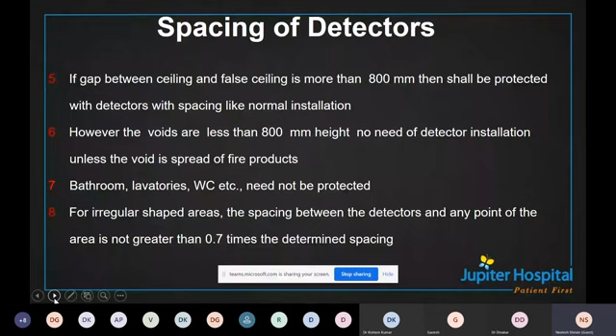So as per the norms, if this is the case, then we need to make sure that we put smoke detectors above the false ceiling and below the false ceiling also. This is mandatory nowadays. So please make sure that if your distance is more than 800 mm, you put both sprinkler and smoke detector above and below the ceiling. Similarly, there is no need to put detectors in a bathroom, lavatories or WC. For any irregular shaped areas, the spacing between detectors and any point of the area should not be greater than 0.7 times the determined spacing.